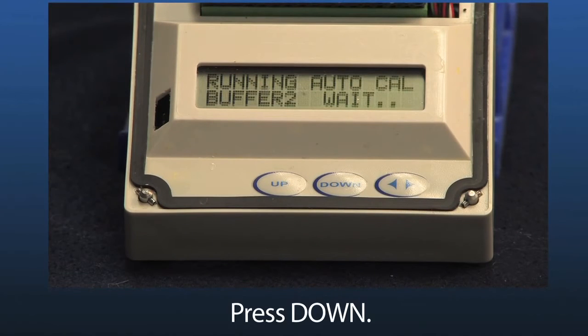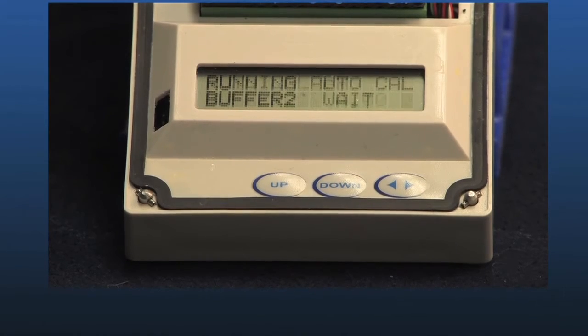It's thinking, and it's measuring the output of the probe, and hopefully it's going to discover it's in pH 4 calibration solution. Sure enough, it does. Now I'm going to hit down, but before I do, let me warn you, because you're going to have to look very carefully. The next display will show you the efficiency of the probe that it has calculated for the two buffer solutions.